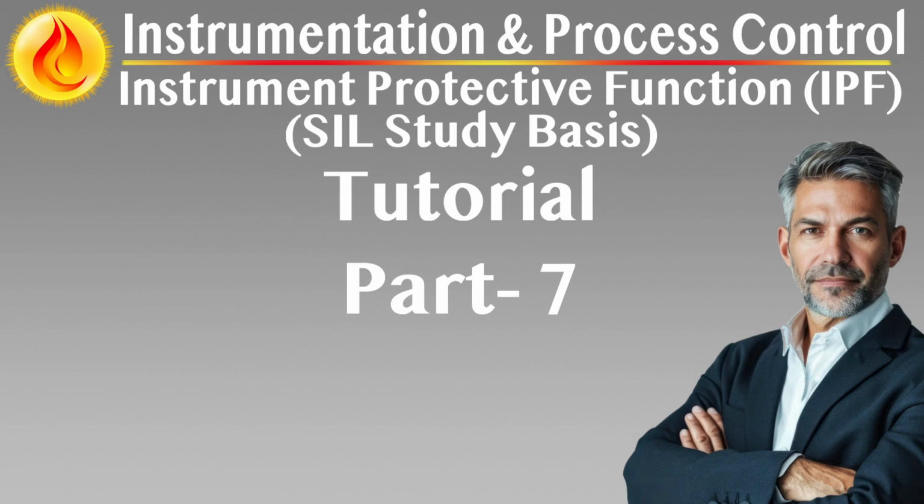Partial stroke testing, PST, applies to final elements, e.g. shutdown valves, where full stroke testing is not possible during operation. Detects mechanical binding or degradation without affecting process flow. Function testing, used during commissioning or after maintenance to verify correct response from input to output. May involve simulation of process conditions, signal injection, or loopback checks. Diagnostic self-testing, performed automatically by smart instruments or logic solvers to detect internal hardware or configuration faults.